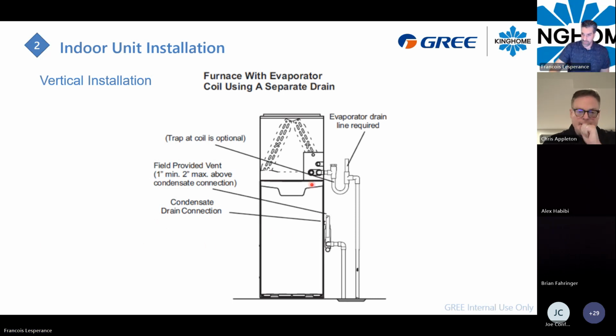Talking about the drain, you have a 3/4 outlet drain by default. The P-trap here on the drawing is optional. When the A-coil is in the supply, you have positive pressure right here, so you don't need to install this kind of trap. But if you go straight, you must make sure you have a small part to reduce the pressure right here. By the flow, the water will drain right here into the floor drain. But you will push some positive air pressure into the drain line as well. So when it's separate from the furnace drain, it's good.